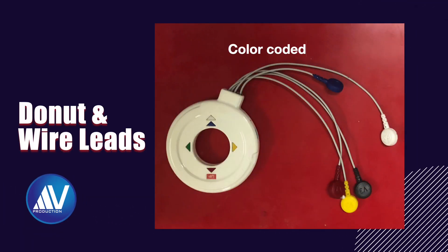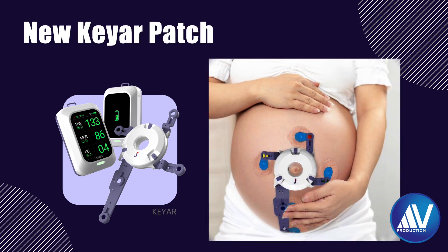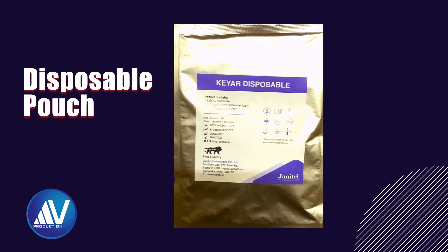This is the donut which has five wire leads coming out of it — they are color-coded. Four of these have long wire leads. The fifth short wire lead is to be connected to the patch that is four fingers above the pubic symphysis, lying directly above the fetal head — equivalent to the fetal scalp electrode of intrapartum fetal monitoring. They have now introduced a new patch device which makes attaching lead wires easy, sold separately. The disposable pouch contains five sets of electrodes, exfoliation tape, and an adhesive ring sticker to be placed on the donut applied over the umbilicus. I will demonstrate how they are applied later.